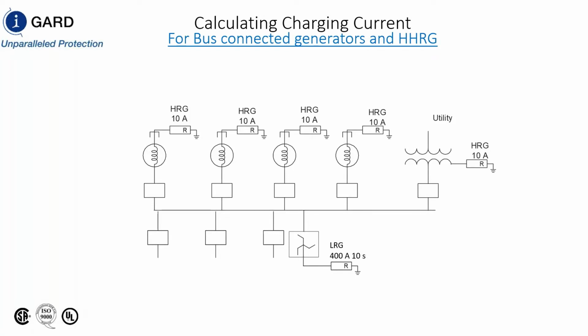Would the same hybrid system apply if you are a generating station that exports to the utility? Would hybrid grounding apply if you are a generating station that exports to the utility? Well, it depends. If you're a generating station, are you generating at medium voltage, or are you generating at low voltage and stepping up to transport to the utility? So there's a couple of things that you have to look at.